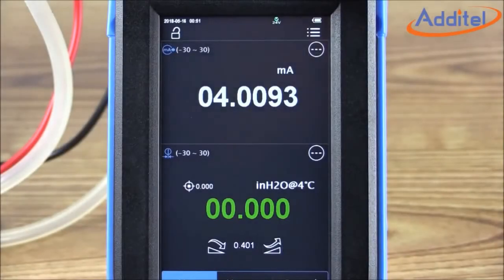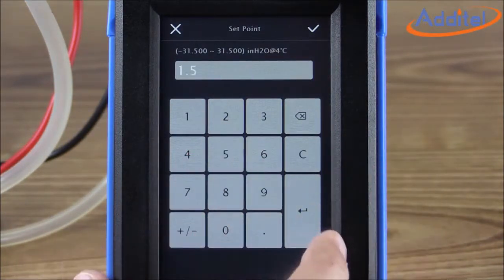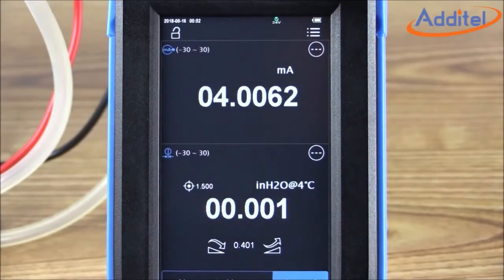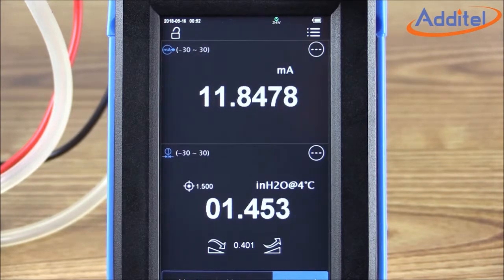Next, we'll want to run a quick test to make sure everything is functioning properly. We'll pick a set point halfway between our upper and lower limits of our transmitter. In this case, 1.5 inches of water. We'll allow the Additel ADT760 to take control of the pressure and closely note the milliamp reading in the box at the top. It should end up somewhere halfway between 4 and 20 milliamps in this case. It looks like it's going to settle right around 12 milliamps, which is a good indicator that things are functioning properly. Now we're ready to move on with our calibration.